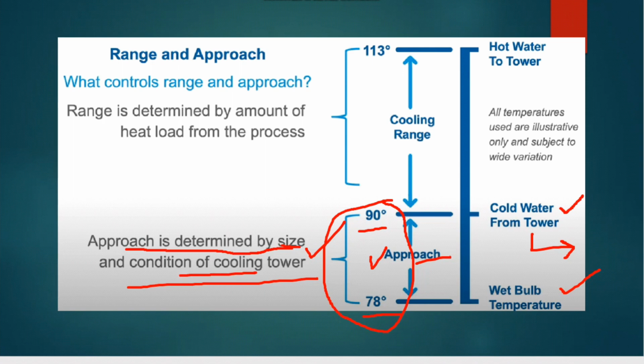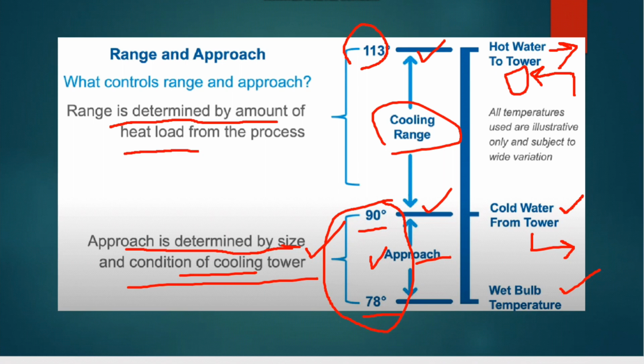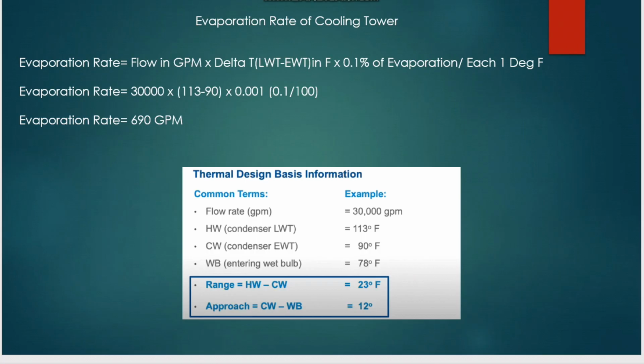Coming to the next one, we have the hot water to the tower. That is the water from the chiller which is entering the cooling tower. It is 113 degrees Fahrenheit in our example. The difference of these two is called the cooling range. This cooling range is determined by the amount of heat load from the process. The process means our overall system. Based on that load, the cooling range will be determined, so there will be some changes in the cooling range based on the load of the system.